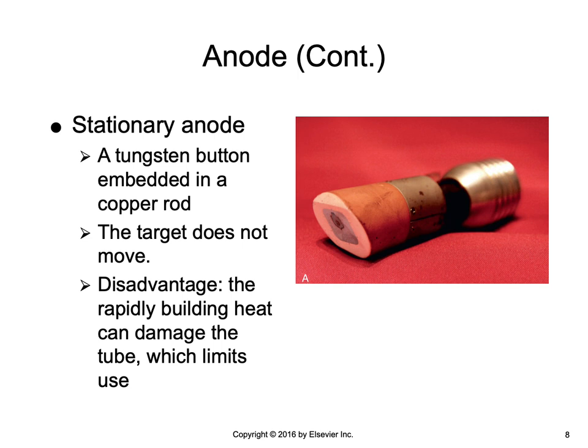Shown here is a stationary anode removed from the glass envelope — you can see the silver-colored tungsten button and the discolored area where electrons interacted with it.